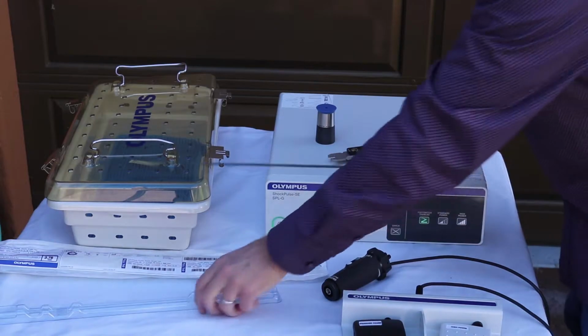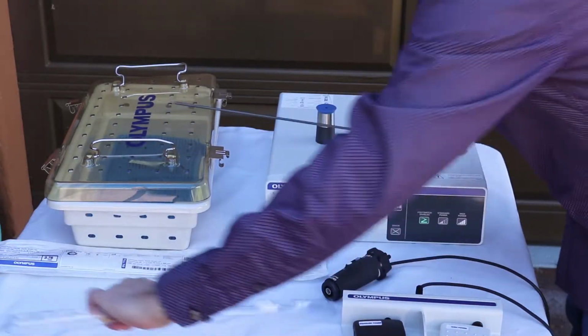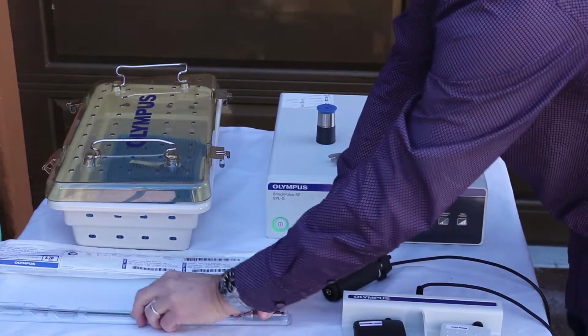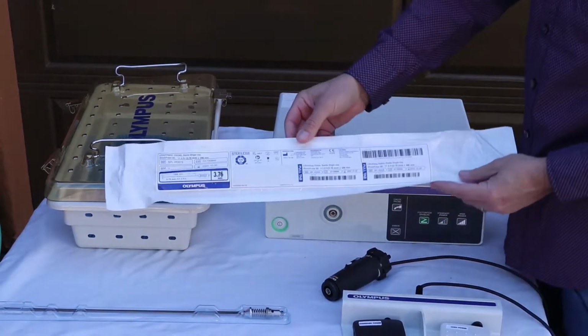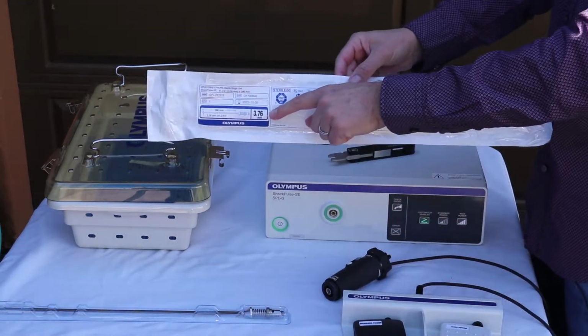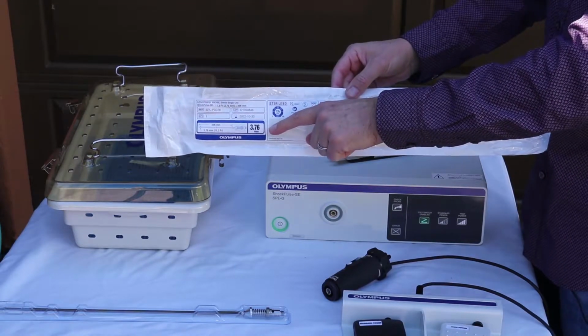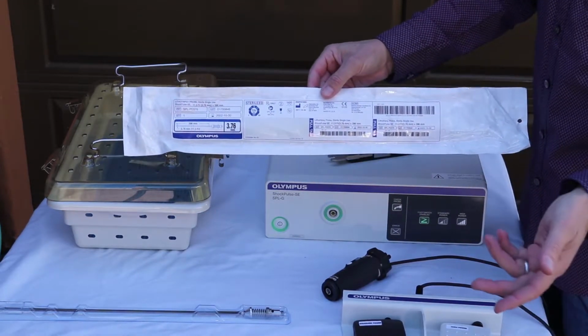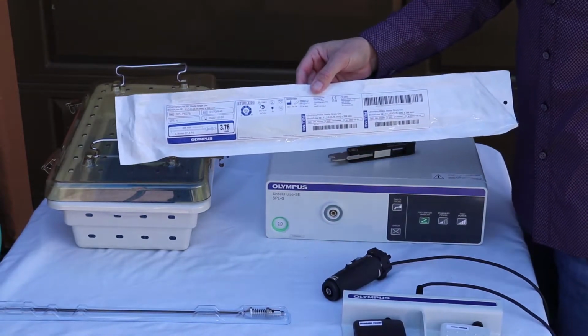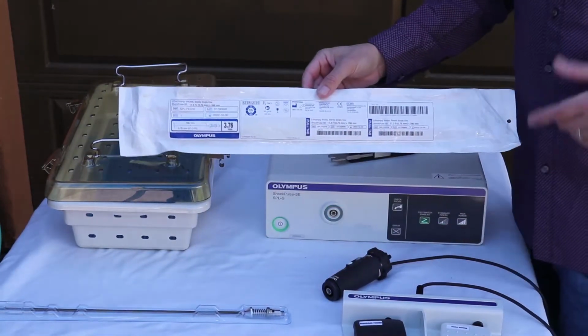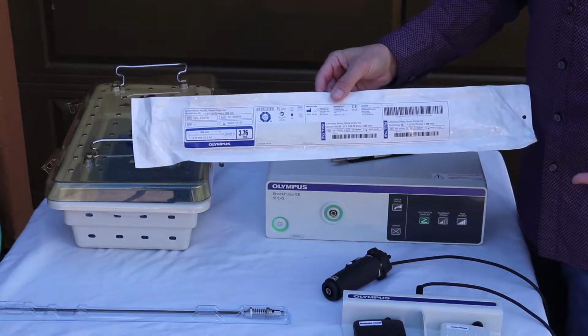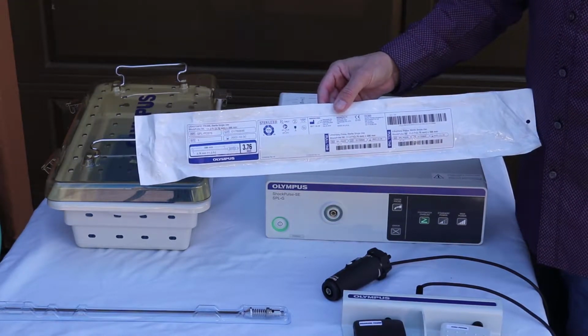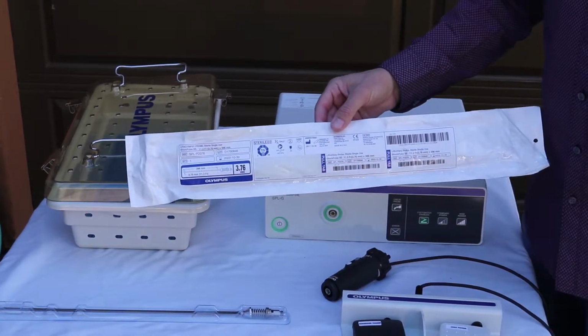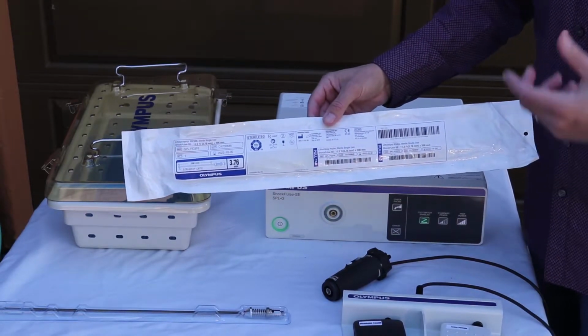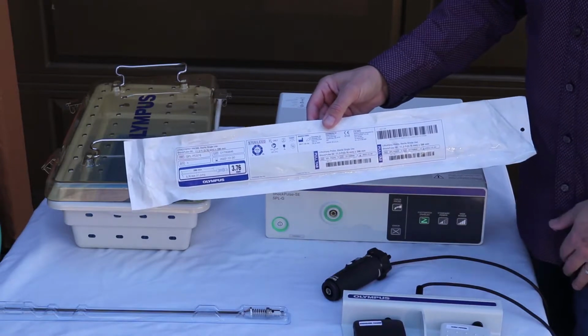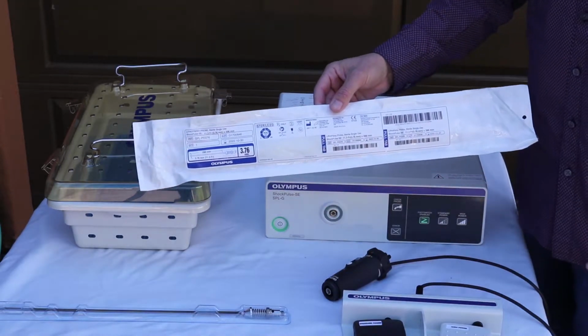Also, the probes do come in different sizes. We have two primary sizes that we use for procedures. This is a 3.76 millimeter probe, and this is the most common one that's used through a nephroscope. We do have a 3.4 millimeter probe as well. It's the same length, and it's also used either in the bladder or in the kidney. That's a little bit smaller, and so it works better if you have not necessarily a mini perc. I think it might be too big for a mini perc scope, but if you have a pediatric scope or something that has a smaller channel, the 3.4 millimeter will fit, whereas the 3.76 won't.